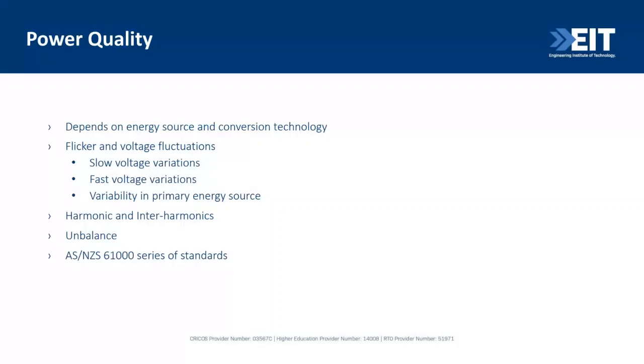Power quality is an important issue, depending on the energy source and conversion technologies. You're going to have flicker and voltage fluctuation—slow voltage variation, fast voltage variation, variability in the primary energy source. Harmonics and interharmonics can come into play, along with unbalanced situations, so you have to look at the standards; the Australian Standard 61,000 series is good to look at.